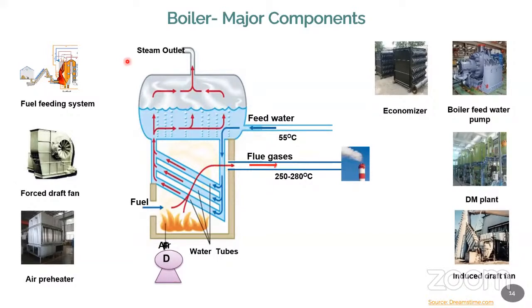then automatically the heat content available in the steam will be let out to the atmosphere. What will happen when it touches the atmospheric air? The atmospheric air will have moisture content, so automatically your steam starts to condense. Before going to the process itself, the steam starts to condense, so water droplets will develop in the pipe. When the water droplets go inside the pipe to the process, the process will be affected. The quality of the process will be affected. Something similar to your compressor: in compressed air, water should be properly let out with the help of a drain valve, or you have a dryer, or a separate drain valve system in the pipeline itself. Likewise, you have some equipment available to let out the water developed inside the steam pipe. Now it should be properly insulated and it will go to the process.